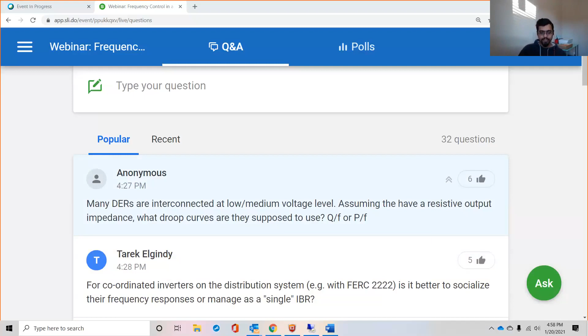With respect to the present 1547 standard, there's capability for both frequency-watt and volt-watt functionality, so you can have change in active power with respect to voltage and change in active power with respect to frequency. Depending on where the DER is being connected, they'll have to decide which droop control is beneficial for that system. I don't think there's a generalized answer for which curve to use, but the capability should exist to use either, depending on where those inverters are connected or which part of the system they're connected to.